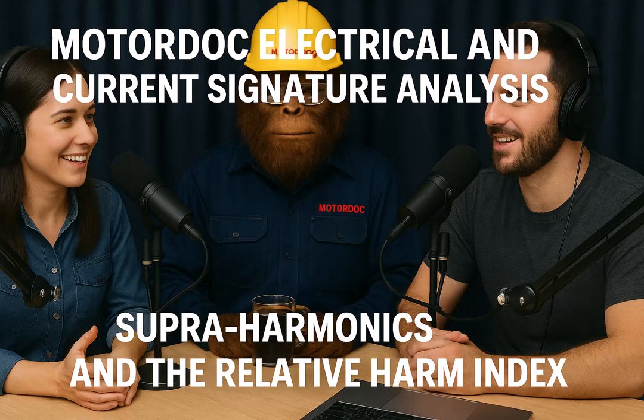Right. Insulation. ESA and MCSA can spot both direct breakdowns and, importantly, the conditions leading to breakdown. Both direct and inferred. Precisely. So in the current spectrum, you can see signatures for things like interturn defects within a coil, physical movement of coils, issues in the rotor windings, even things related to the stator slots. They all leave unique spectral marks. And does the size of that mark, the dB level, tell you how bad it is? Generally, yes. The higher the dB level of a specific defect signature compared to the normal background noise, the more severe the condition is likely to be. So it's quantifiable. It gives you a quantitative idea, yeah.